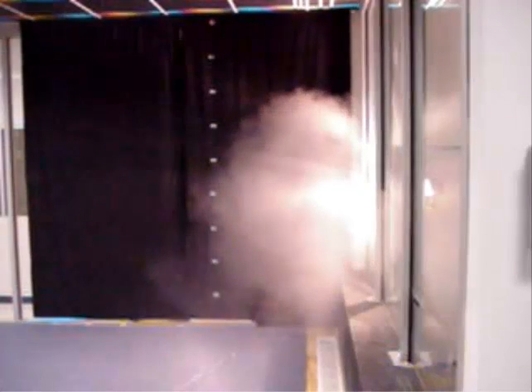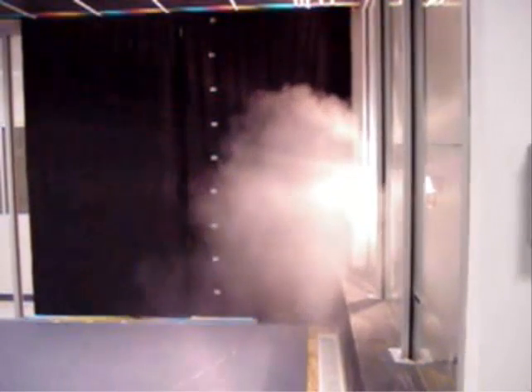This video illustrates the unit during operation at 225 CFM, maintaining a 6-foot throw above the floor. Each one of the marks in the black background is 1 foot apart. As you count the marks, you see from the smoke that the throw settles at 6 feet. At the peak of the throw, the airflow rolls over on itself due to the tri-deflection grill and moves into the space to cool the occupants.